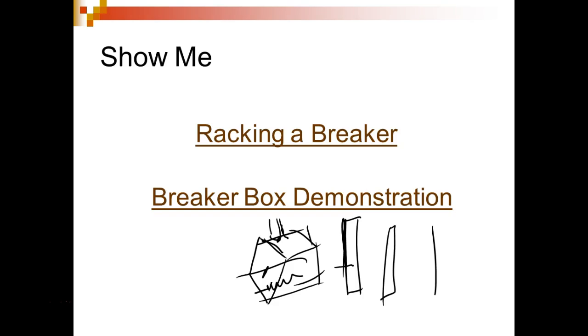The way breaker panels are set up now, they rack them through the door, so they close the doors and latch them down, then rack them through the door. So if you have a blast, it's going to come into that door. It might blow the door off, but it's a lot better to be hit by a door than it is what you saw there.